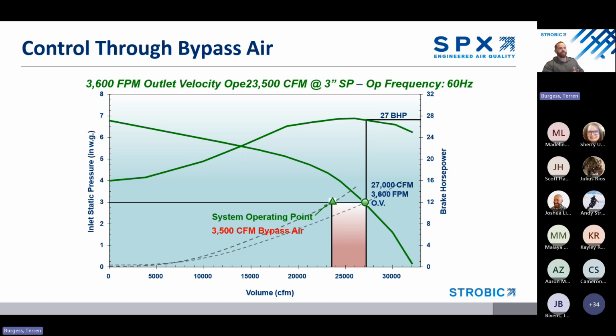And it works. I mean, it certainly does work as a sequence, but here's the catch. All that bypass air is clean ambient air that you are processing through the fan system, and that's going to translate to wasted energy. So that's why, when I talk about systems like the Strobic Air Safe system, they're designed to reduce or even eliminate bypass air when feasible. So with the variable speed fan, smart control logic, and the appropriate fan sizing, we can keep that plume safe. The effective plume rise continues to exist, but we're not wasting energy with the injection of too much bypass air. So it's safer, smarter, and a lot more efficient.